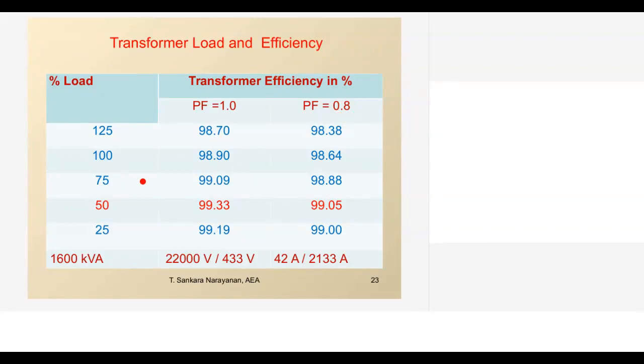So if you go by the manufacturer information, these transformers can have higher efficiency at 50% load. If the load increases, there is a difference in efficiency which can go up to 0.7% or 0.4%. So what is this indicating? As an auditor or as an operating person, if I have a lesser load on a transformer, it is not that I am losing too much energy.